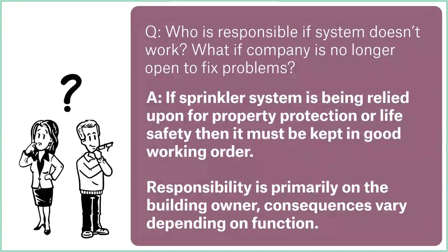Responsibility is basically down to the building owner. And so the consequences will depend on the function. If it's an insurance job, then the consequences of not maintaining that sprinkler system might be that your insurer gives you a slap on the wrist, or your insurer doesn't cover you in the event of a fire. So that's going to be a financial penalty. If it's for life safety and you don't keep it in good working order, if there's a fire and there's injuries or even deaths, then of course that will come with a different set of consequences, which could result in imprisonment and very, very severe punishments. So building owner is the short answer.